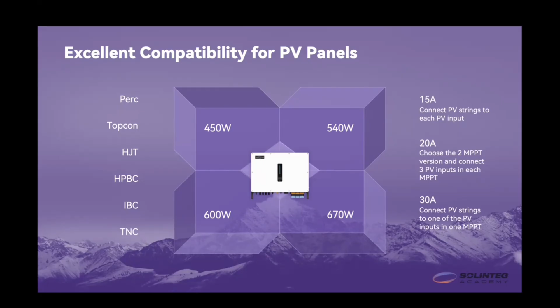So next, let's see how to set these different PV input solutions. If all the PV strings we want to connect have less than 15 ampere input current, we can just connect each PV string to a different PV input on the bottom of our inverter. We can just connect the PV string to the PV input port over here. In this case, the maximum PV input current our inverter can accept is 15 ampere.